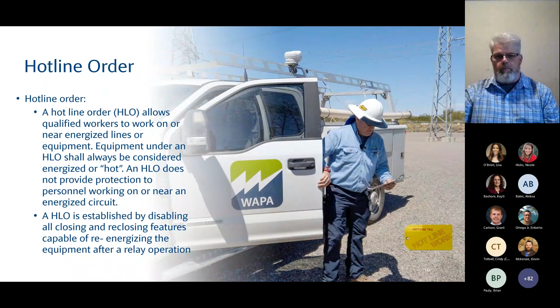When we have to work on equipment that's hot, we turn off the reclosing relays, the 79 relays, and then we place a hotline tag or light on the device. We go through the formal process of issuing the HLO supervisor this hotline order. Again, it provides no protection—it's just when we're forced into working on equipment that is energized. And guess what the most important part of this is? Right after safety, it's constant communications between the system operator and the HLO supervisor.